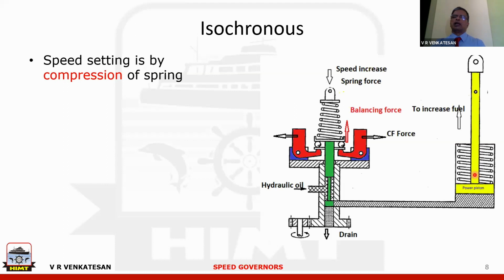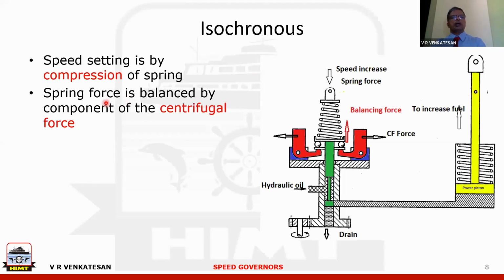If the power piston moves in this direction, the fuel will increase. This valve is called the pilot valve. So if the pilot valve goes down, hydraulic oil will flow into the power piston cylinder arrangement. If the pilot valve moves up, the oil from here will be going to the drain. This is the simple working principle of the centrifugal governor. So how it is going to work is the speed setting is by compression of the spring. Then the spring force is balanced by the component of the centrifugal force.